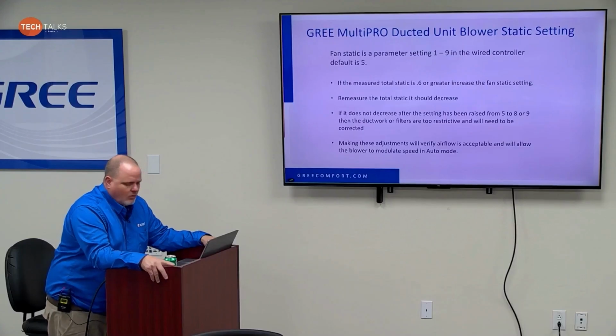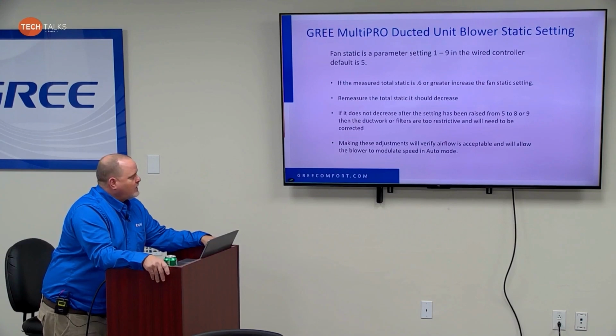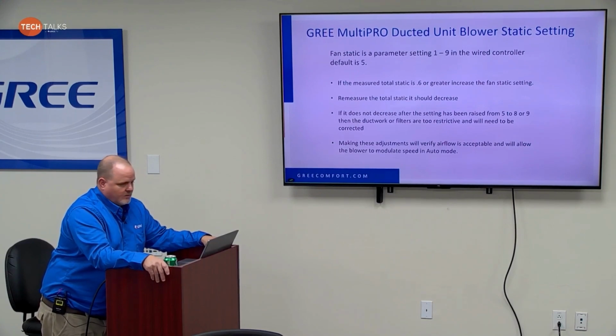Or maybe you're doing it on a PM and you're checking the static. If the filter's clogged, it'll do the same thing, okay? But it's very important that we set that. I've had some guys say, well, I just tell them to turn it up to 9. That's a bad idea, because now you just gave that blower the full torque setting, and now it's not going to modulate because you don't have the ductwork. What I mean by that is if you set it to 9, but your total static was only at like 0.4 or 0.5, you've given that blower that full torque setting.